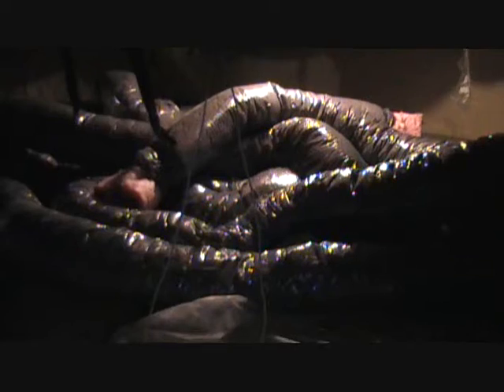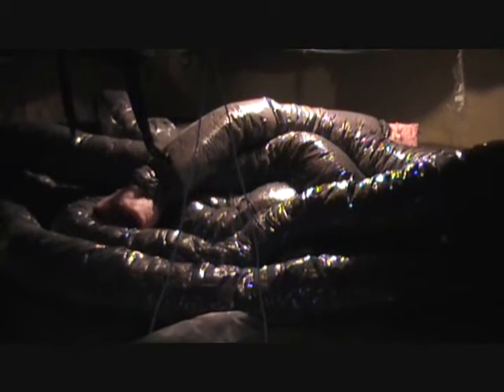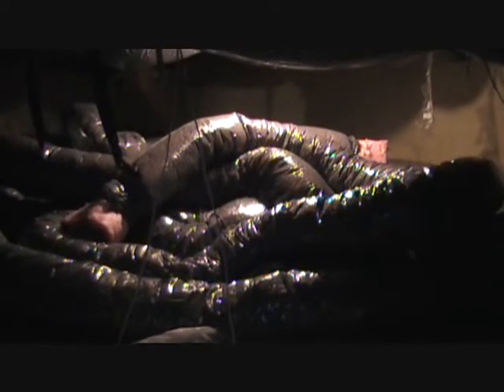With the length and all the bends in the flex, there were return air runs that were over 200 feet of equivalent length in this crawl space. And I would wager that the supplies are even longer than that.